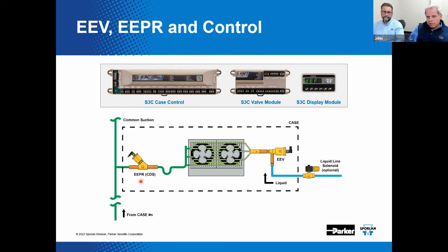Indeed. The case control will handle the normal case functions and receive the necessary sensor inputs for the EEV, and the valve module, like we've said before, will drive the EEPR. The EEPR could regulate discharge air temperature, and the EEV will simply control superheat. That optional liquid line solenoid valve may be installed as 1 per case or 1 per lineup, if you will. And again, I've given my thoughts on the optional part of it. Each case in the lineup could theoretically be fitted with its own EEPR and valve module. Indeed, they could. And we'd sure probably like that if you'd do that.